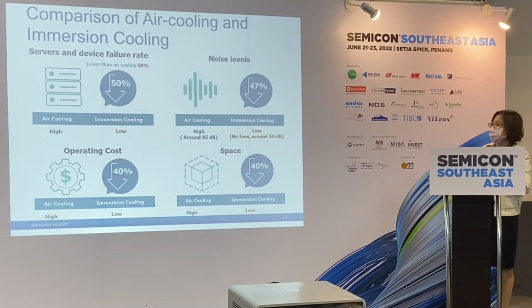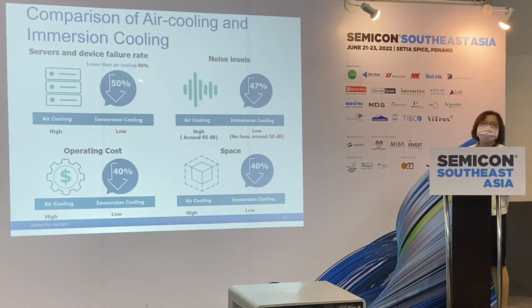Next, because we use no fans, the devices and the servers don't have as many failures. So the failure rate will be lowered by 50%. And because we don't use fans, there is no noise. For air cooling, as we measure, usually it is 95 decibels, but for the immersion cooling system, with no fans, around 50.